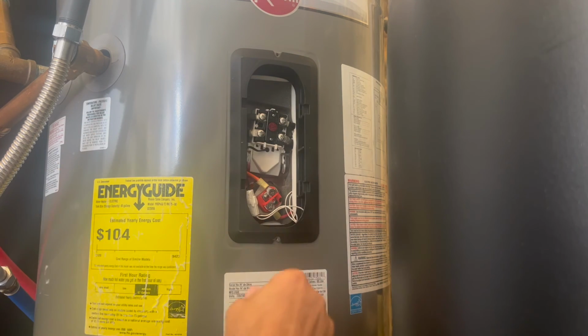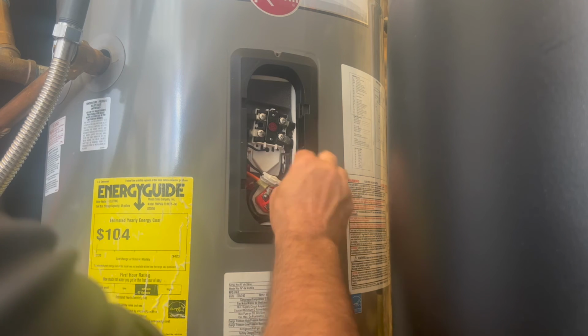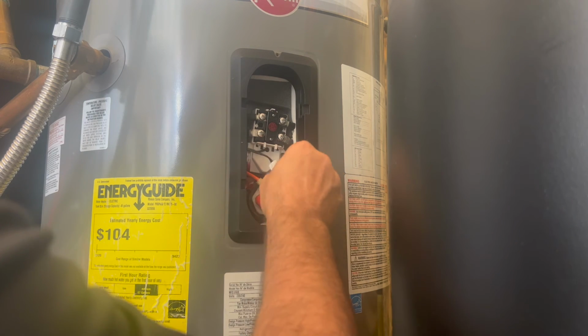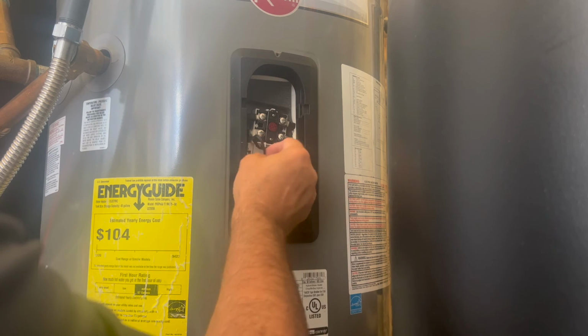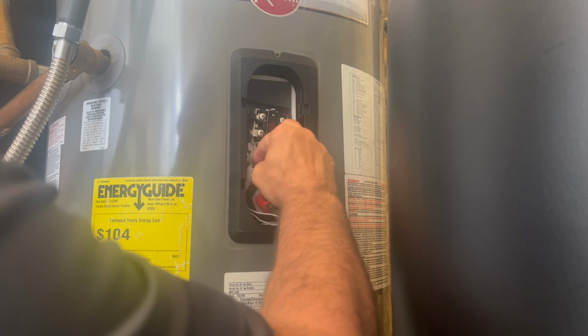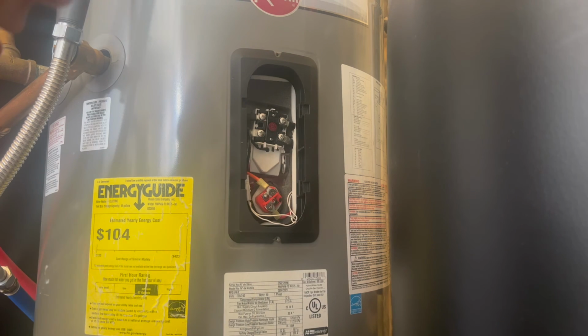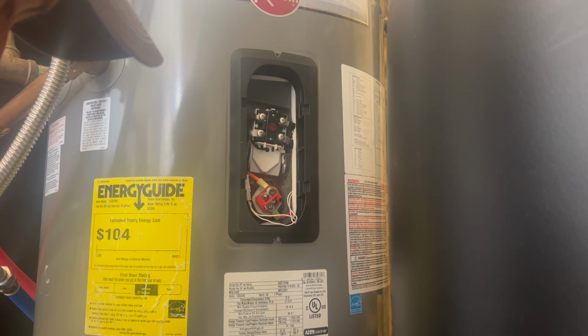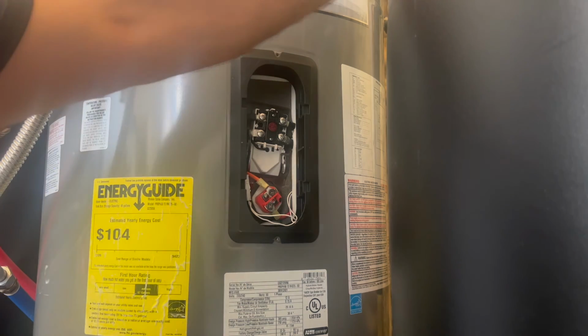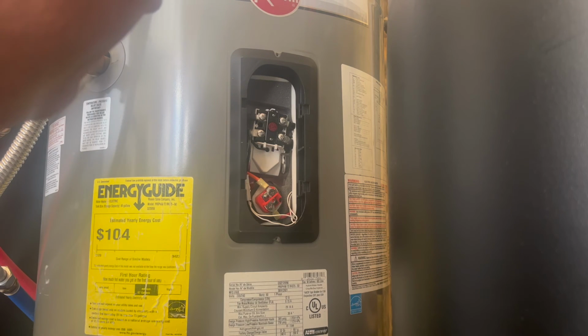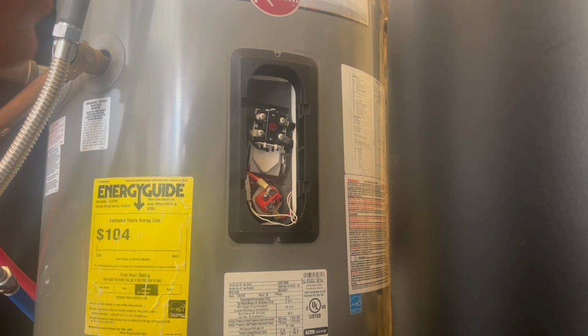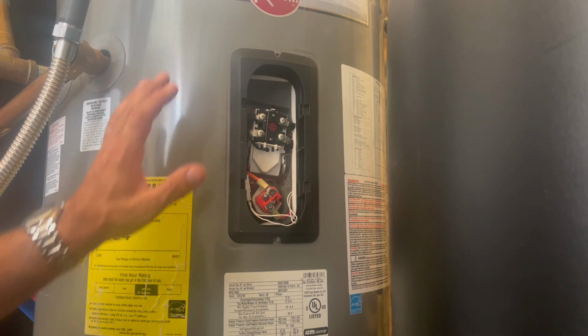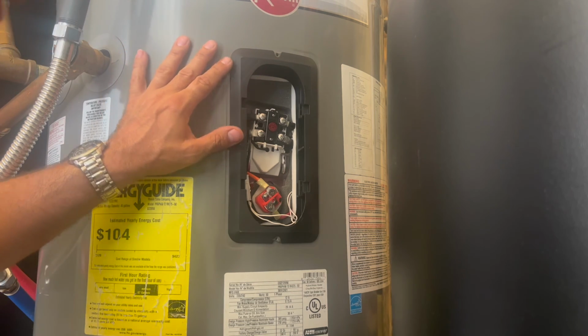Okay? Down at the bottom, the sensor plug is there. That's in another video where you can access the sensor for the water leak detector. And then also the thermistor. They're down there easily accessible. You can ohm those out. Verify that you've got a good reading on those. If you're not getting a good reading, you can replace the thermistor, check the wiring. If you're not getting good readings up top on those thermistors, you can replace those thermistors as well.